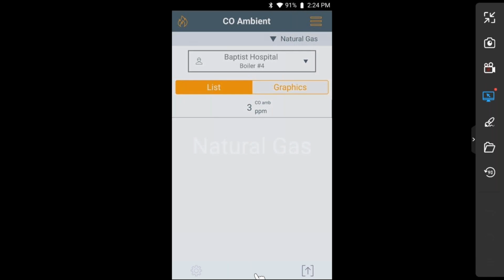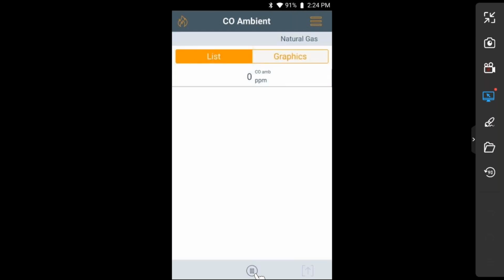I'm going to press the pump. I'm bringing in a sample right now, and this is where I do a sample of carbon monoxide in the breathing air. If you're using this in a residential application, you could be in a home right now, checking where the living area is. If you're in a boiler room, you're checking in a mechanical room where personnel, the maintenance people are, and you're checking carbon monoxide in that area as well.